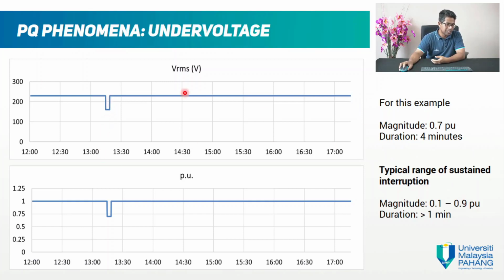For this example, it starts from something like 1 o'clock to about 4 minutes, at 0.7 pu. The voltage goes down until 0.7 pu. This is the thing about power quality: when we say magnitude, we are not discussing how much it lost, how much the voltage goes down. No, we're talking about the remaining voltage. In this case, the remaining voltage is 0.7 pu. Always talk about the remaining, not how many percent the voltage dropped. So the remaining voltage is 0.7 pu and it lasts for 4 minutes.